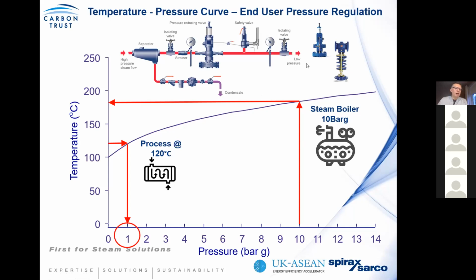Another reason why you reduce pressure is that you get greater controllability by temperature and pressure regulating valves for end users when you have a lower differential pressure across the system. So you get better control. The choice of the pressure reduction station will be determined by the criticality of the pressure. So you can go from self-acting controls to fully automated controls with digital controllers.